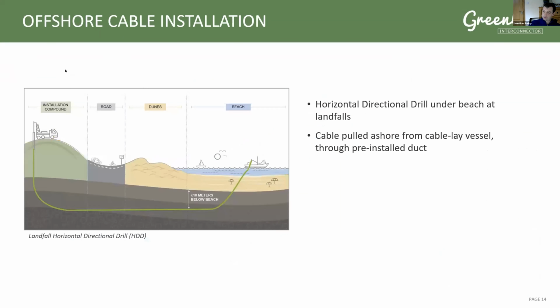And then finally, one of the biggest engineering challenges, and one of the most interesting from a civil point of view, is this horizontal direct drilling. We're not going to dig through the beach at either side. So we're using horizontal direct drilling to drill from a field on land, down to about 10 meters below sea level, and out to the cable lay vessel, and we're going to pull ducts back through and then pull the cable through those ducts. That's a really interesting engineering challenge behind the cable installation on this.